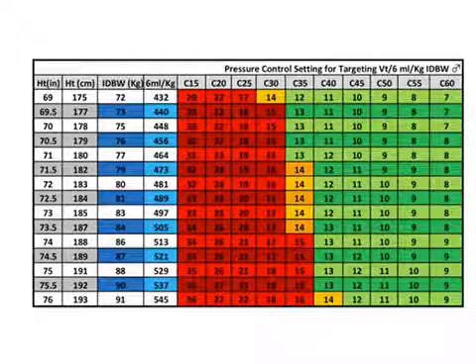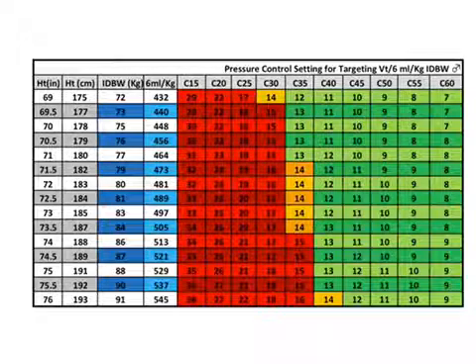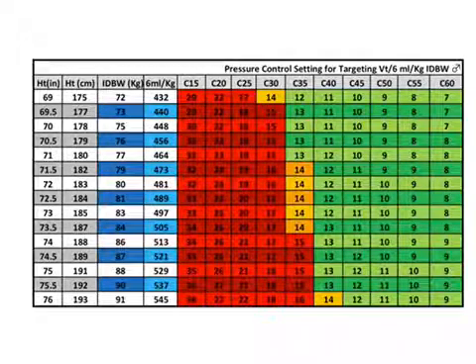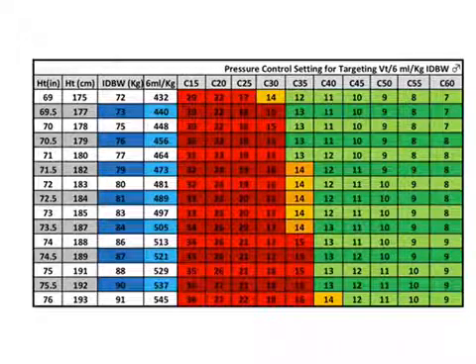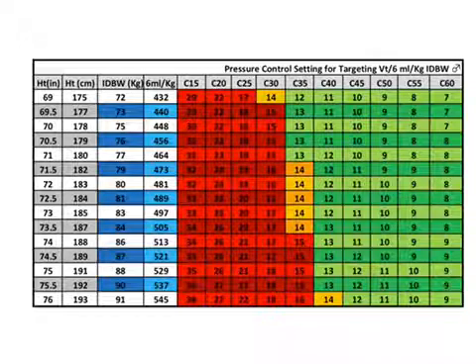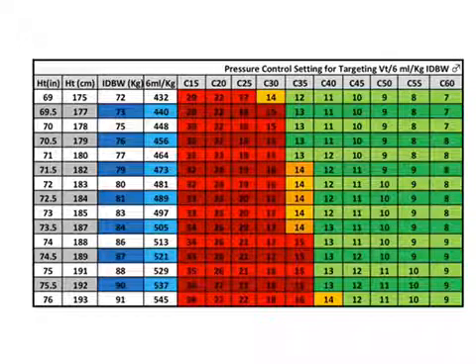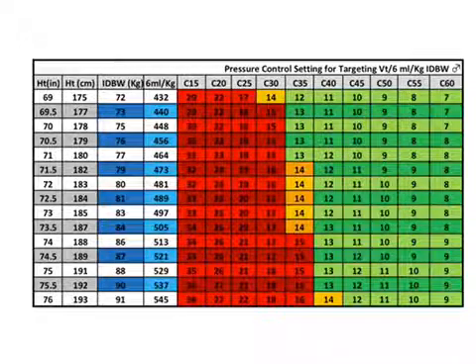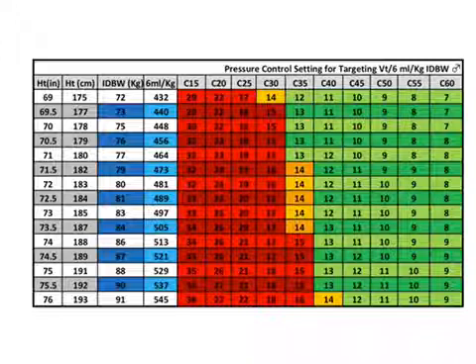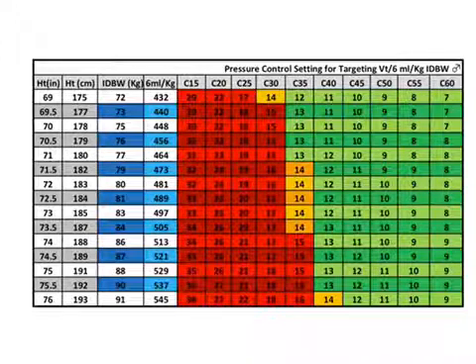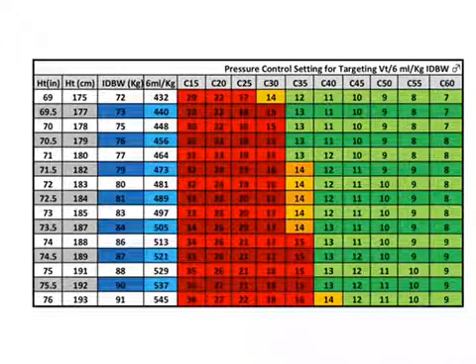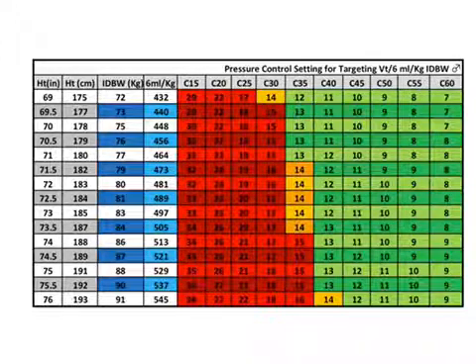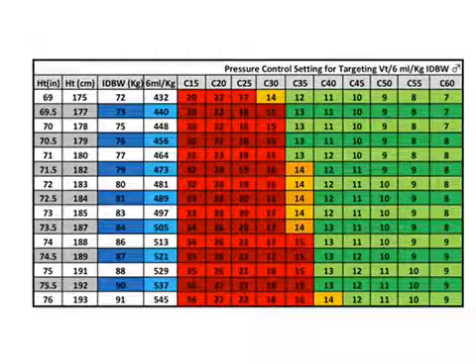The set of tables, pressure control setting for targeting tidal volume per kg per ideal body weight displays the relationships between tidal volume, compliance, and pressure control setting. These tables can be used a few ways.